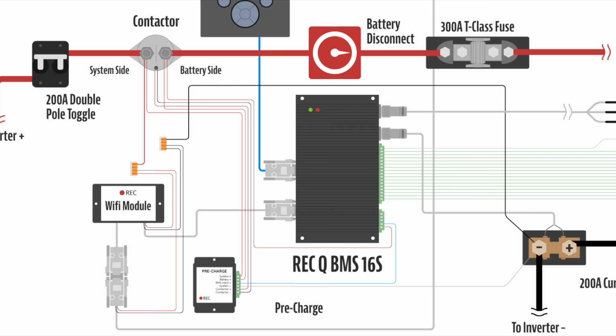And prolongs the contactor lifespan dramatically. For the BMS wiring harness, you only have 2 connections: one that goes straight to the battery side of your contactor, and one that goes to the BMS input positive on the pre-charge unit.